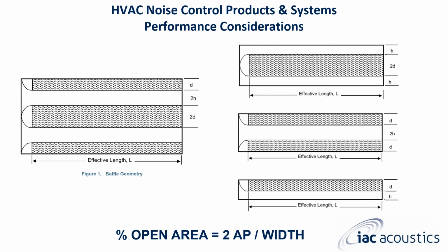So the number of baffles and air gaps only affects the flow area, as does the height and or the span of the baffle. Having more baffle arrangements within the silencer, you will then have more flow area. You'll also then have lower air gap velocity, resulting in lower pressure loss.